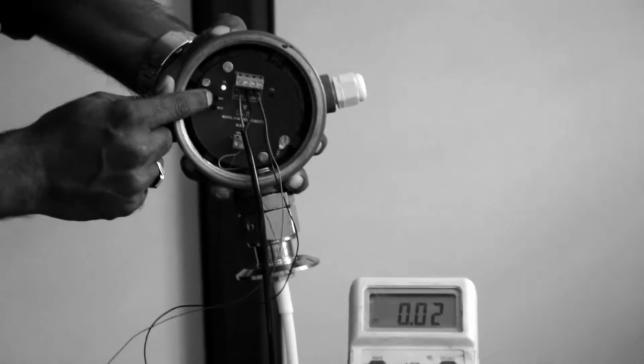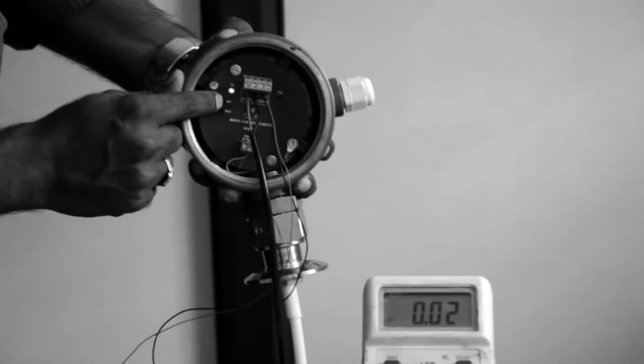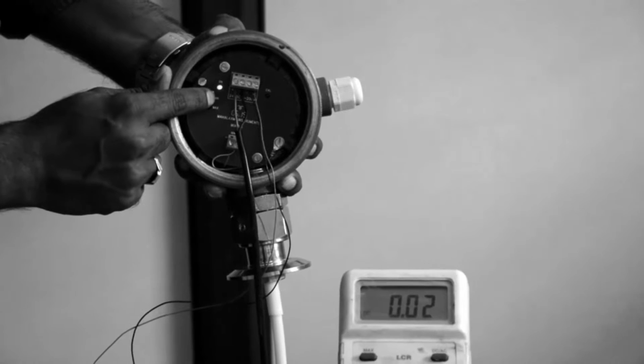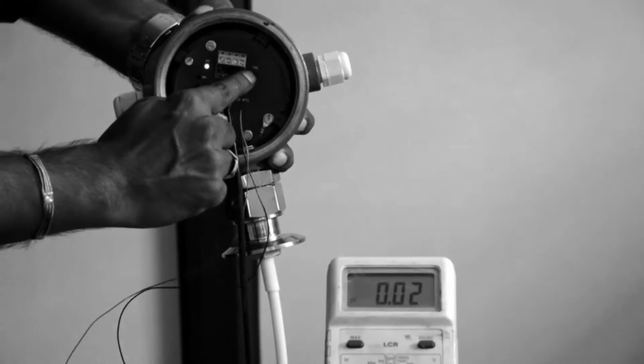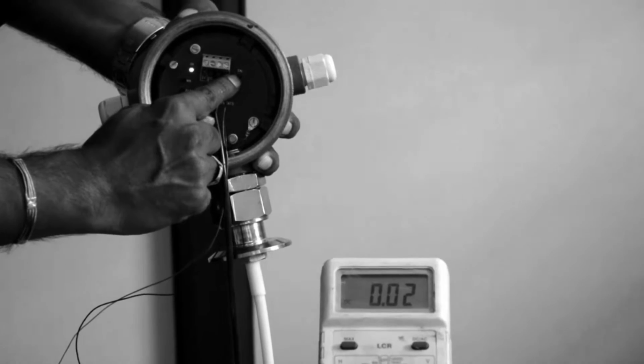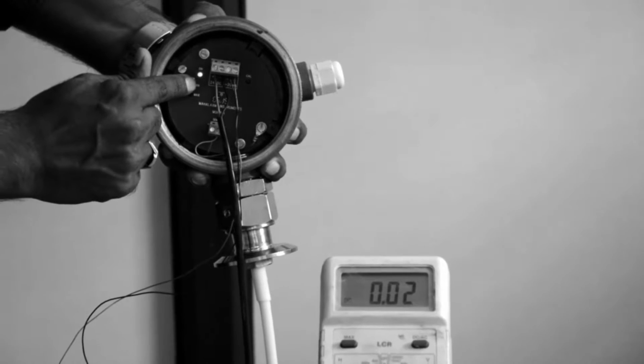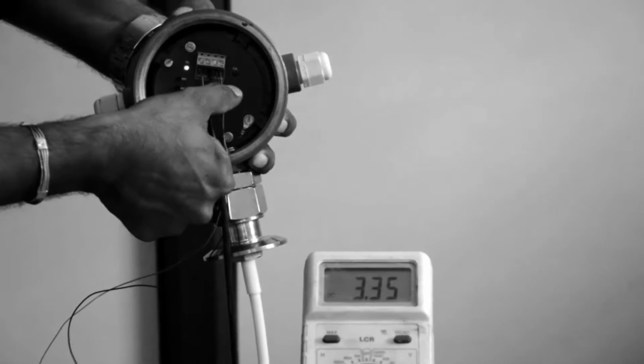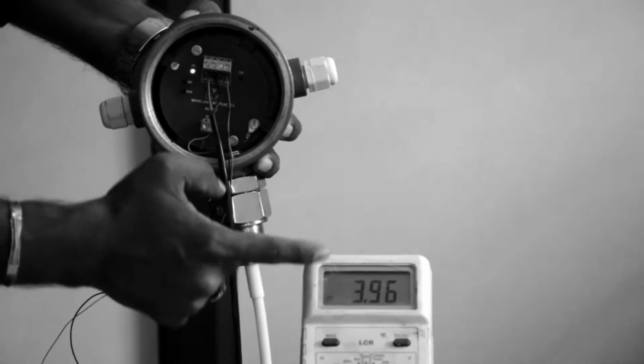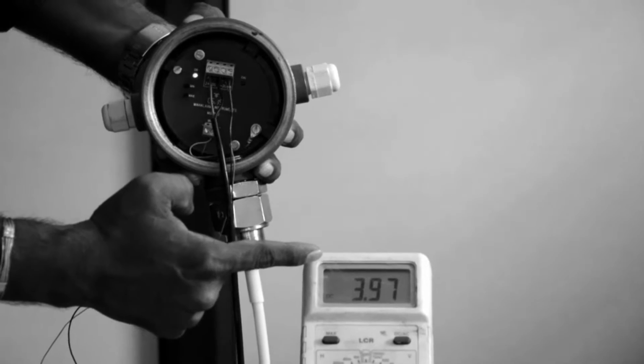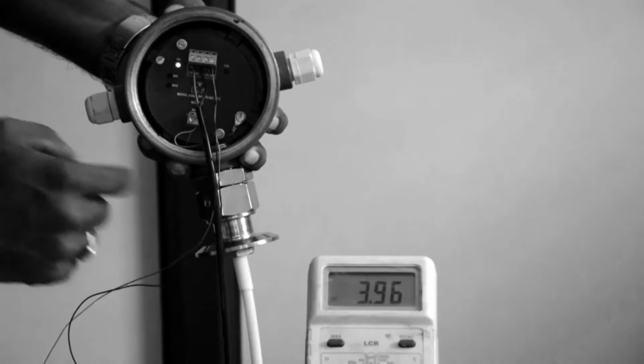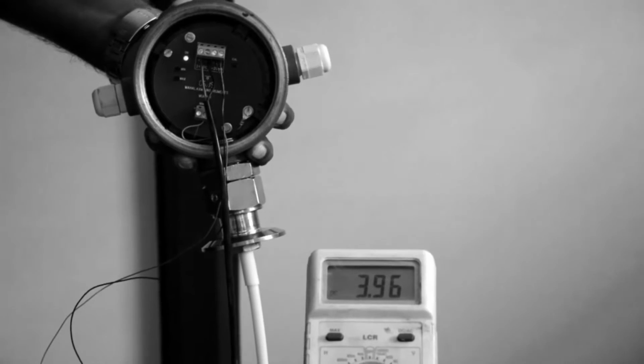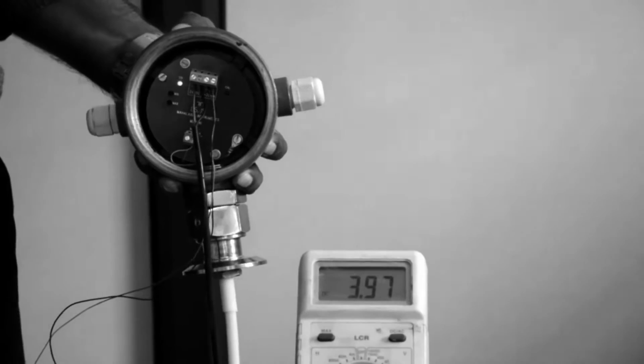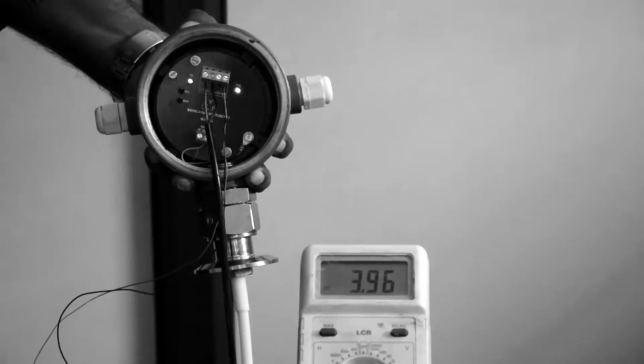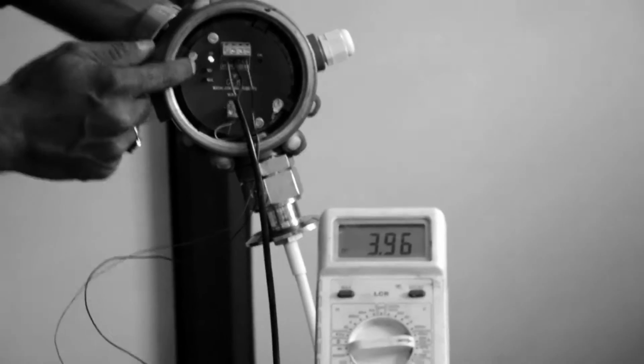What we are going to do first is we are going to push the minimum push button for 3 seconds and hold it. After 3 seconds you can see that the calibration LED will start blinking. I am pushing the minimum push button for 3 seconds. The calibration LED is blinking, and you should be able to see 4 milliamps on your multimeter, but it's showing us 3.96. So what we need to do is we have got to increase this value to 4.